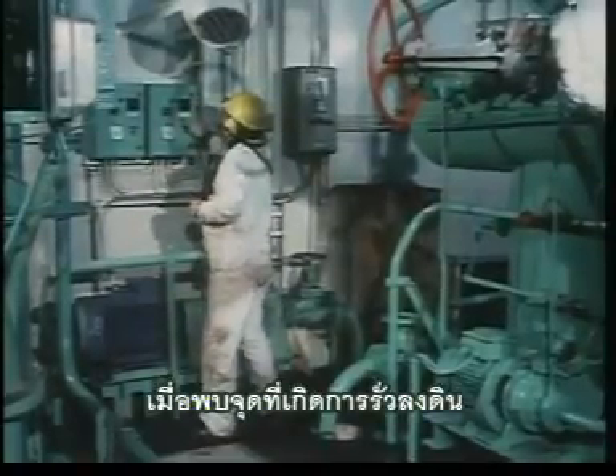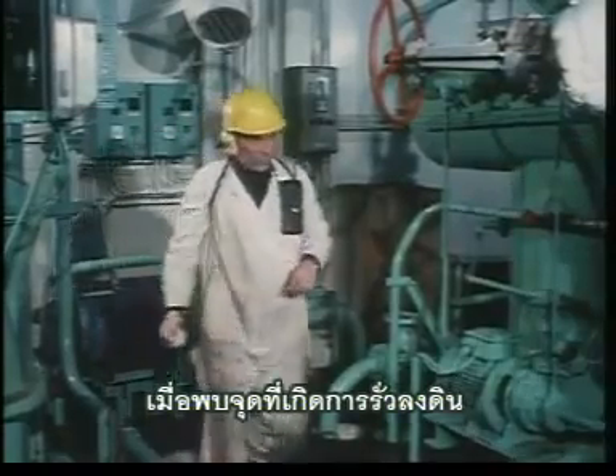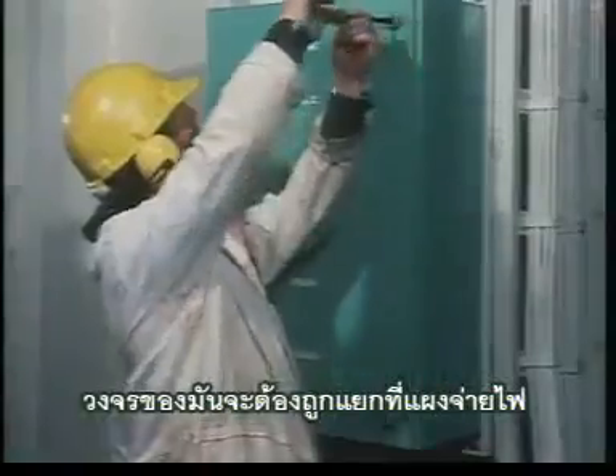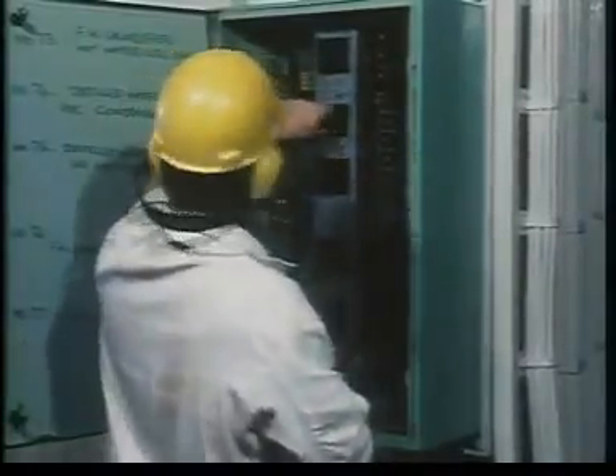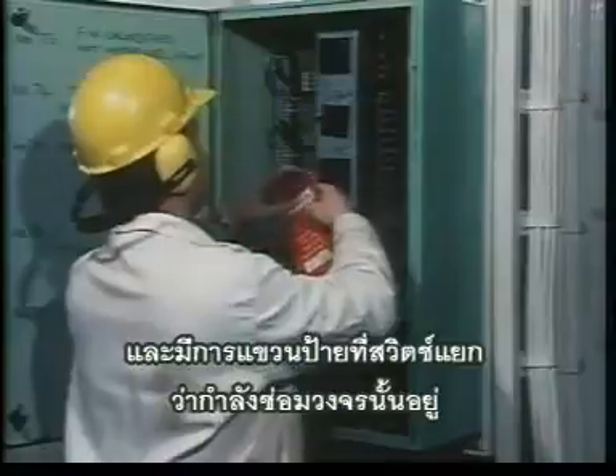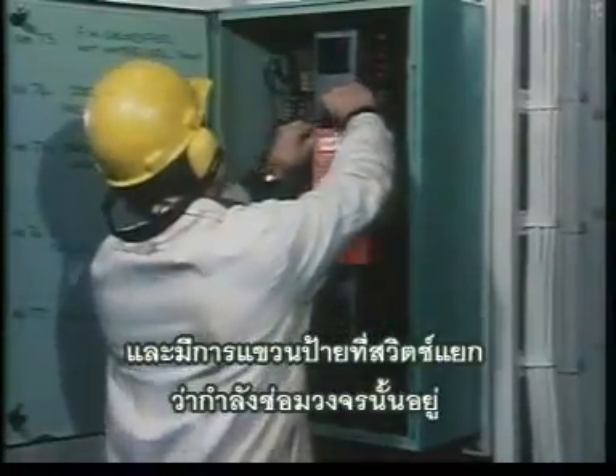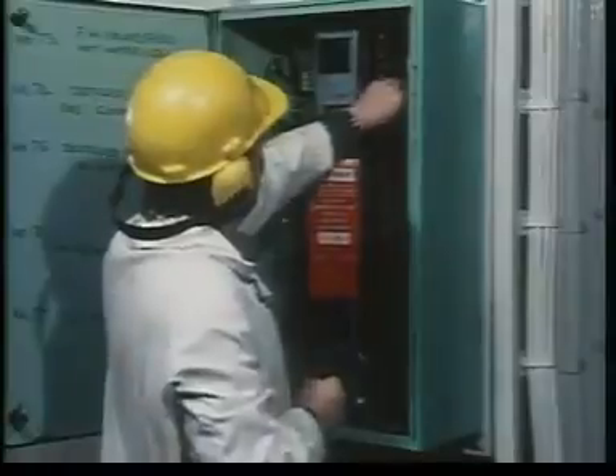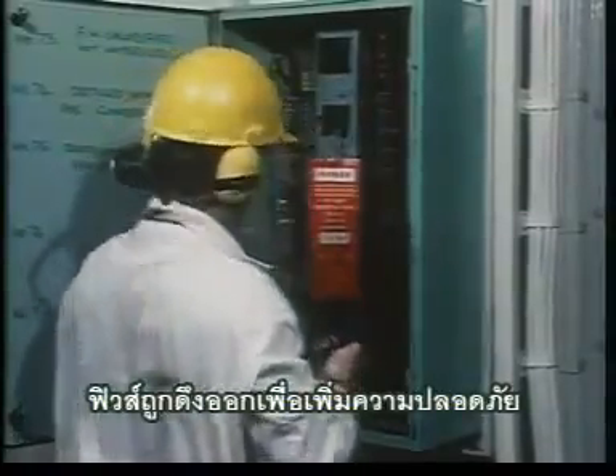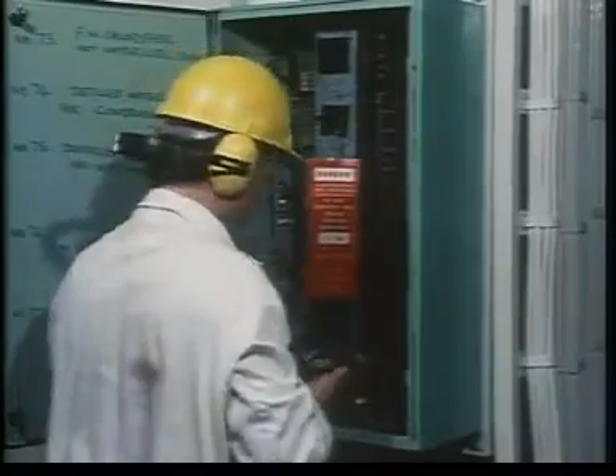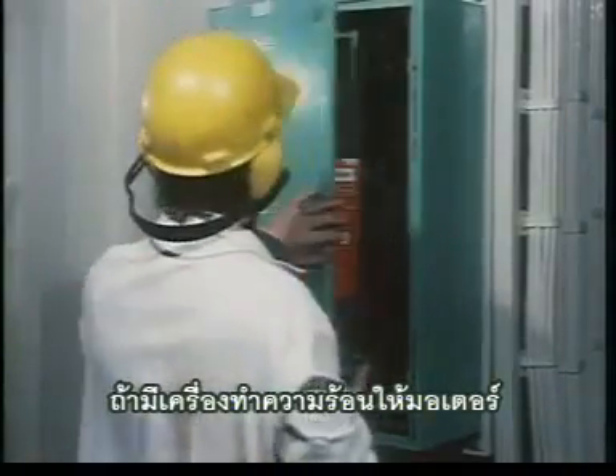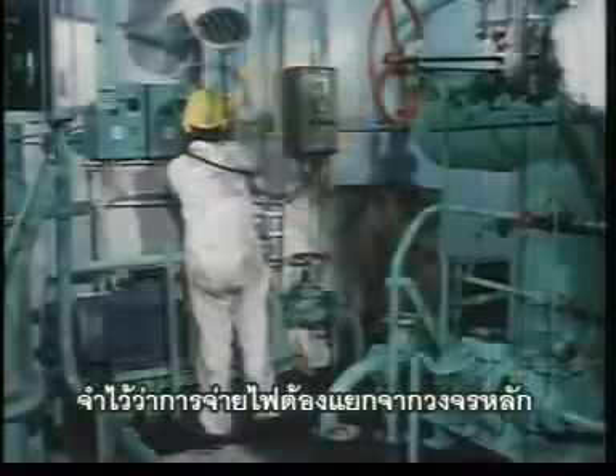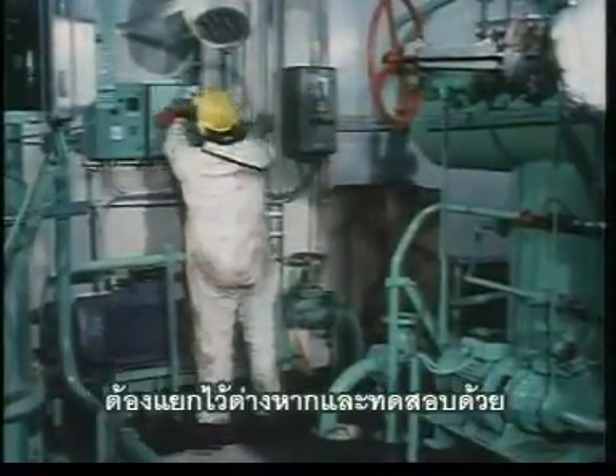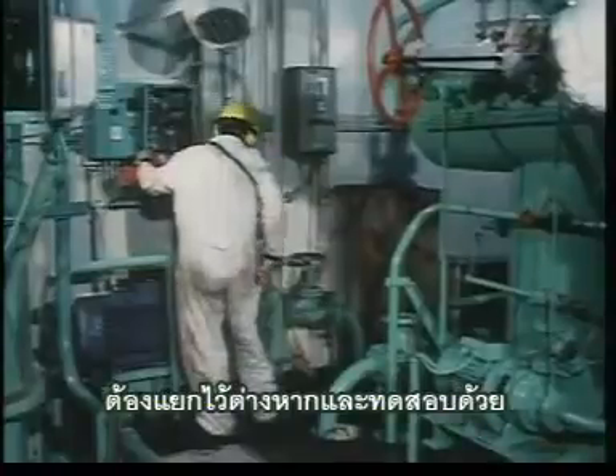Once the actual outgoing circuit is found where the earth fault has occurred, its own circuit can be isolated at the distribution board. And a notice is posted on the isolator switch that the circuit is being worked on. The fuses are removed as an added safeguard. If motor heaters are fitted, remember their supply is usually separate from the main feeder circuit. They must also be isolated and tested.